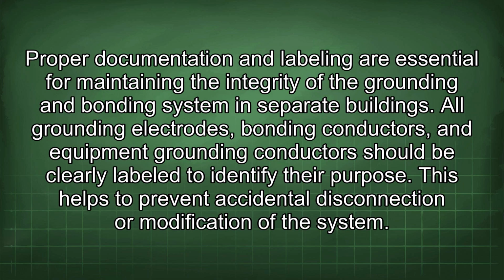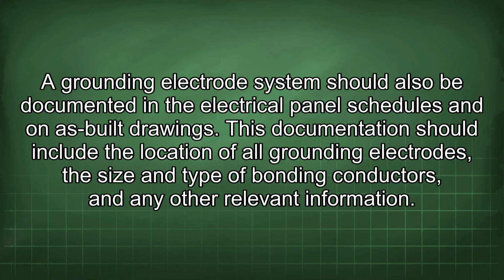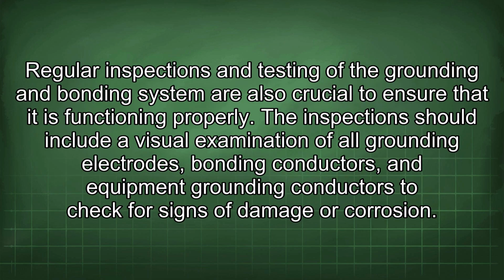Proper documentation and labeling are essential for maintaining the integrity of the grounding and bonding system in separate buildings. All grounding electrodes, bonding conductors, and equipment grounding conductors should be clearly labeled to identify their purpose. This helps to prevent accidental disconnection or modification of the system. A grounding electrode system should also be documented in the electrical panel schedules and on as-built drawings. This documentation should include the location of all grounding electrodes, the size and type of bonding conductors, and any other relevant information. Regular inspections and testing of the grounding and bonding system are also crucial to ensure that it is functioning properly. The inspection should include a visual examination of all grounding electrodes, bonding conductors, and equipment grounding conductors to check for signs of damage or corrosion.